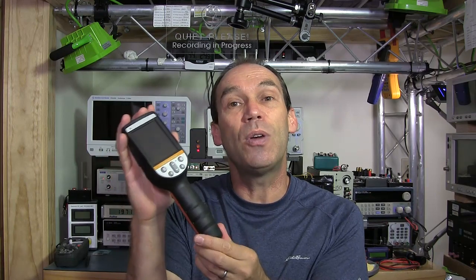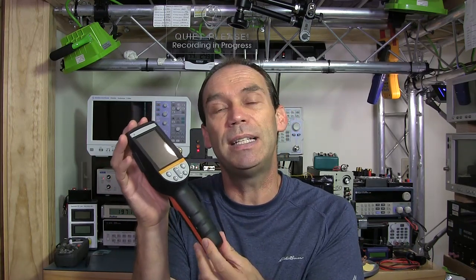The price point of these cameras is anywhere from $180 up to about $220, which seems like a nice entry point. You're not going to expect too much — the resolution is only 32 by 32. It's got a fairly narrow field of view, but that's actually good for the resolution it has. It has quite a few features which remind me of the Fluke VT series, particularly the Fluke VT-04. The resolution, field of view, and blending of visual and thermal image are very similar to the Fluke VT-04.